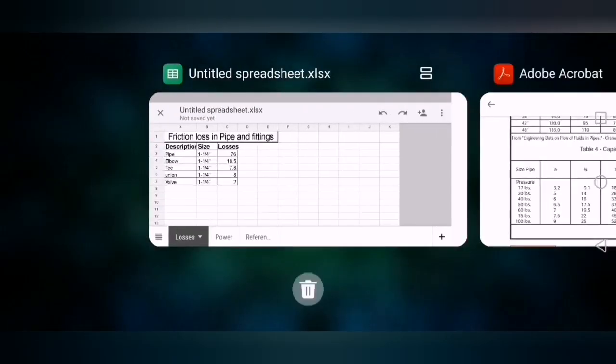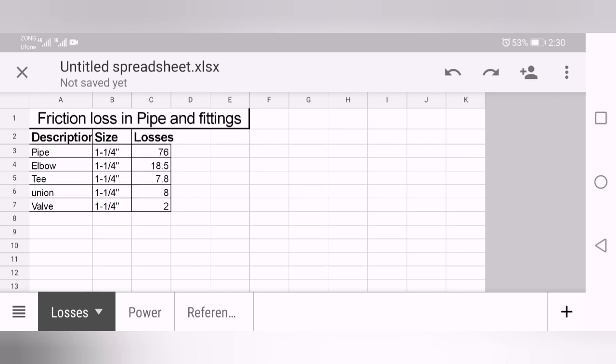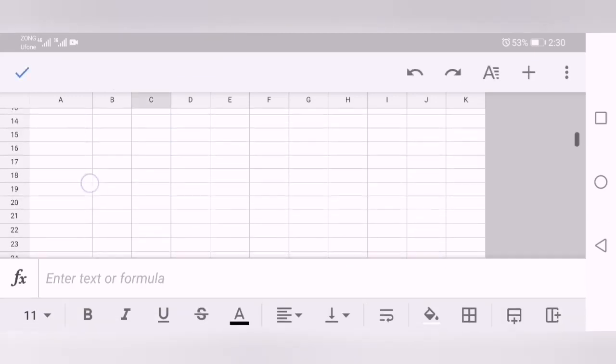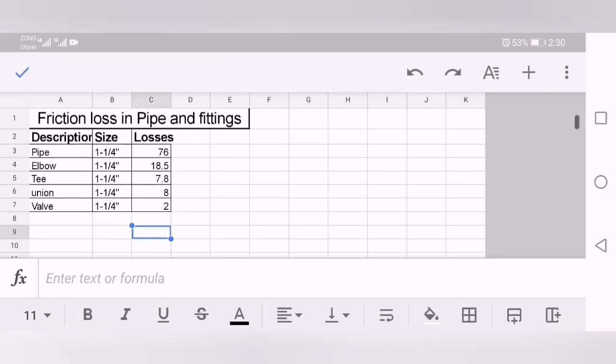So you just note down all of these: pipe head loss, elbow head loss, tee head loss, and calculate it by adding these losses. These losses will be your dynamic head. For total dynamic head you need two things: one is static head and second is the dynamic head or the fitting losses. So just add up these fitting losses and you will get the sum value.